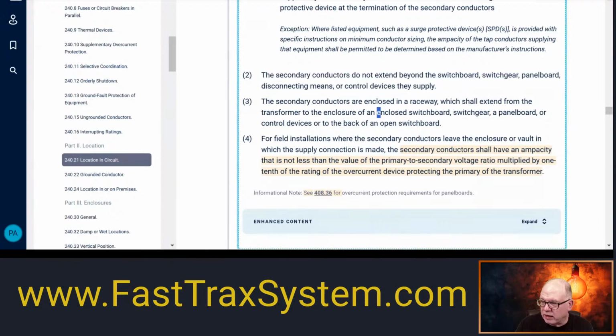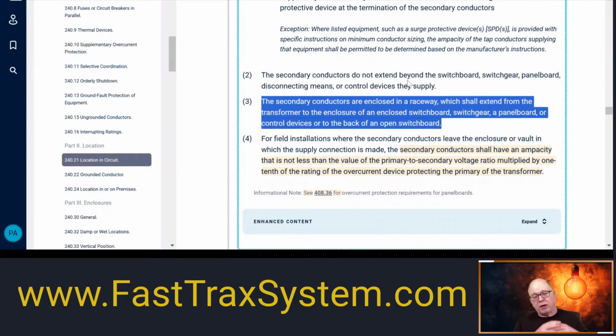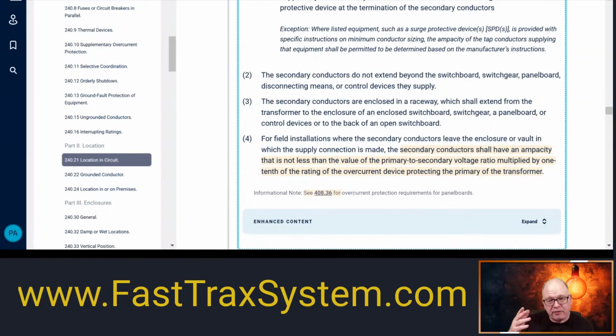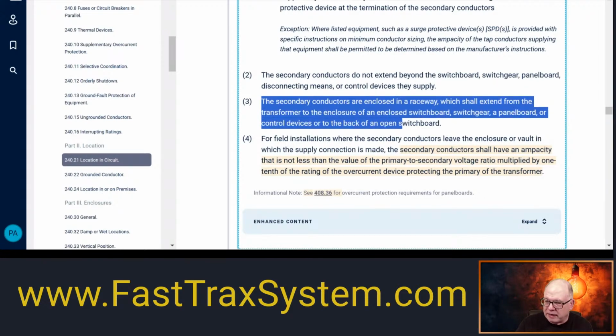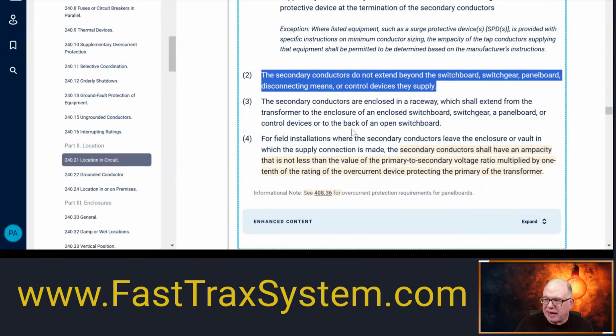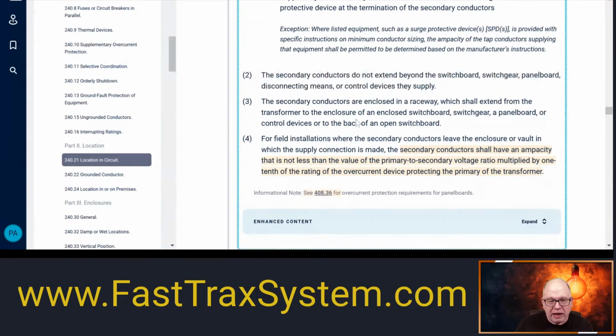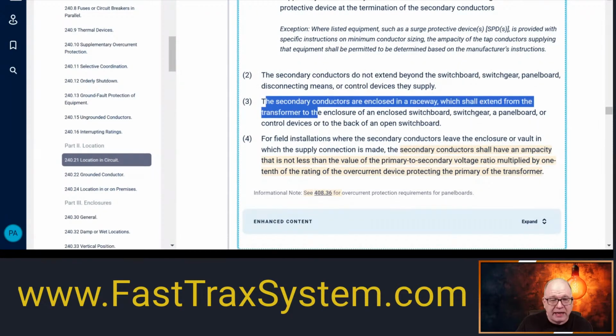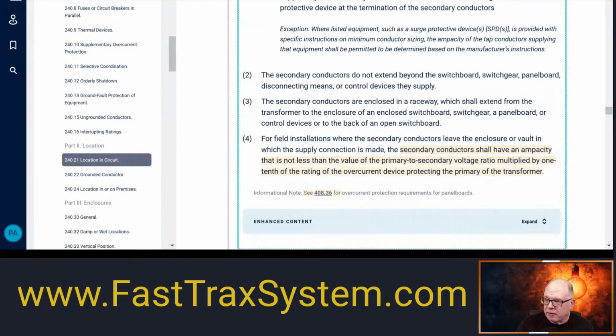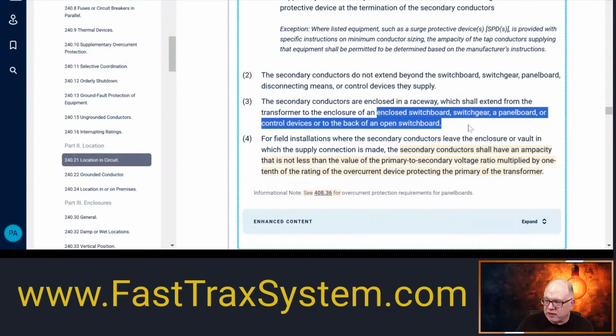But I think, for all intents and purposes, we know what we're talking about. We're coming from the transformer and we're going to the equipment, and it needs to be enclosed in a raceway. Again, talk with your AHJ, have a conversation. If we want to do what Dan said, let's say, and put a disconnecting means, then I think we just have to realize, and there's people out there that say, well, the words matter, Paul. I get it, but here it talks specifically about the secondary conductors and how they should not extend. And here it's trying to tell you how they get from point A to point B. I think you're going to actually be putting in a raceway, even though you don't see the words disconnecting means here. I think you're going to be extending it in a raceway.